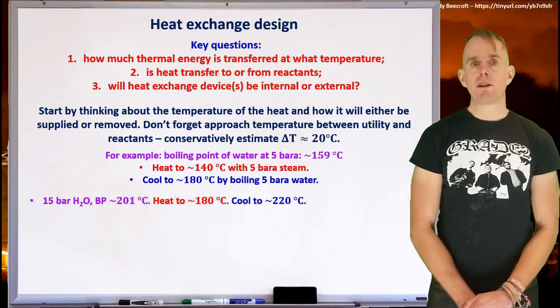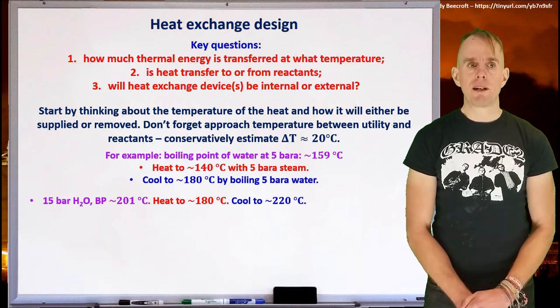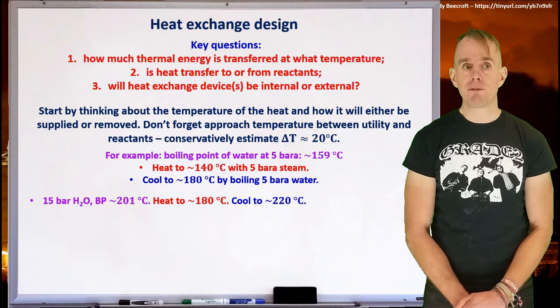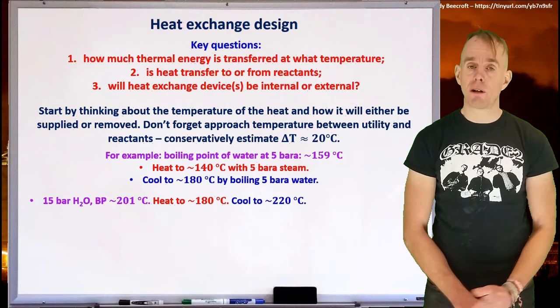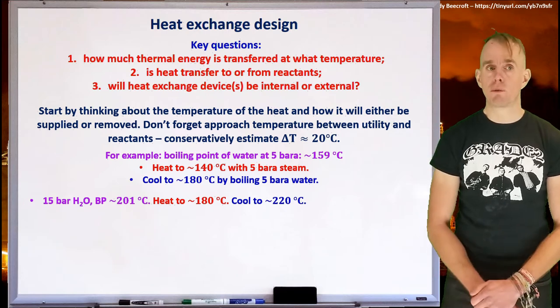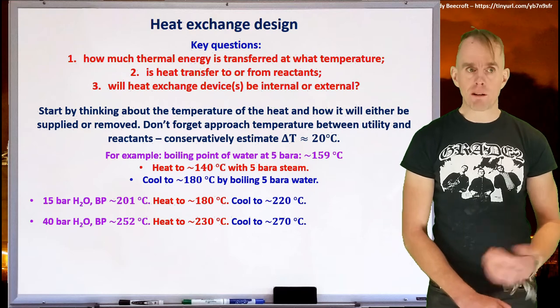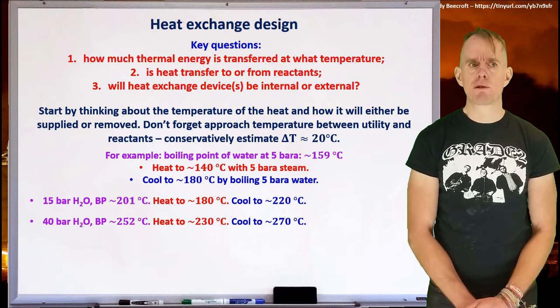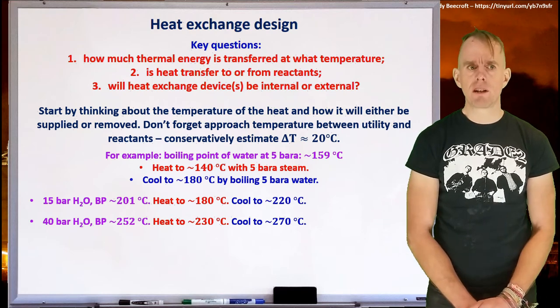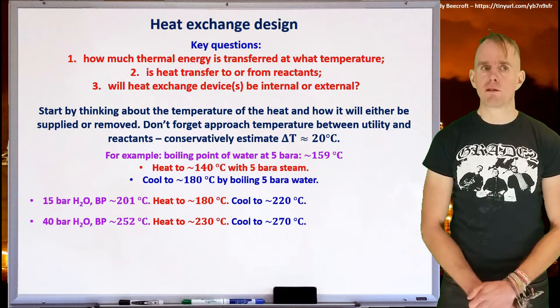In a similar vein, if we think about intermediate pressure steam or intermediate pressure water, you'll find that the boiling point at 15 bar is just a touch over 200 degrees C. So you can heat to 180 or cool to 220. Likewise, for high pressure steam, typically 40 bar or thereabouts, the boiling point of water at 40 bar is 252 degrees C. So you can heat to 230 or cool to 270.